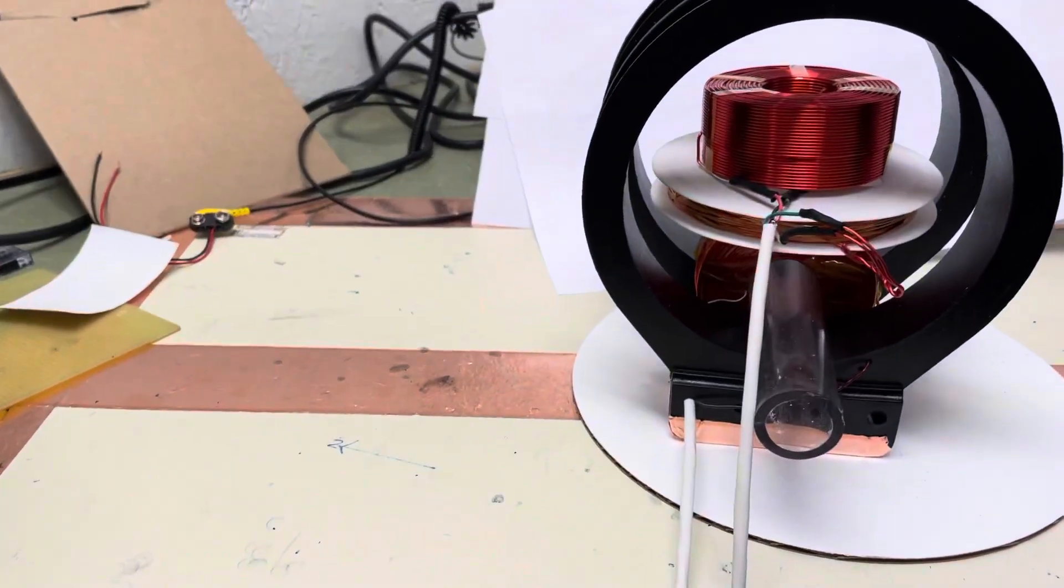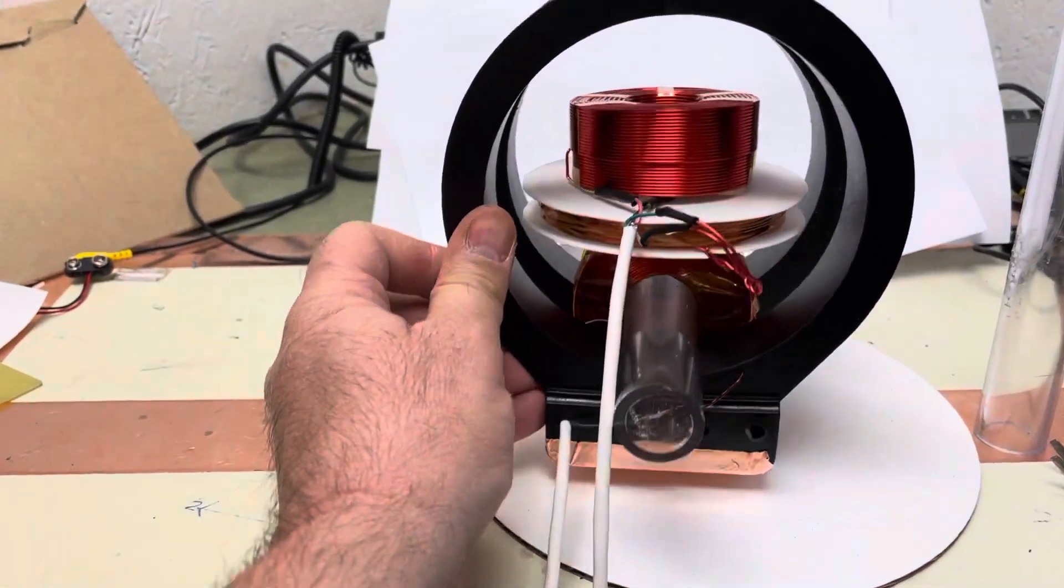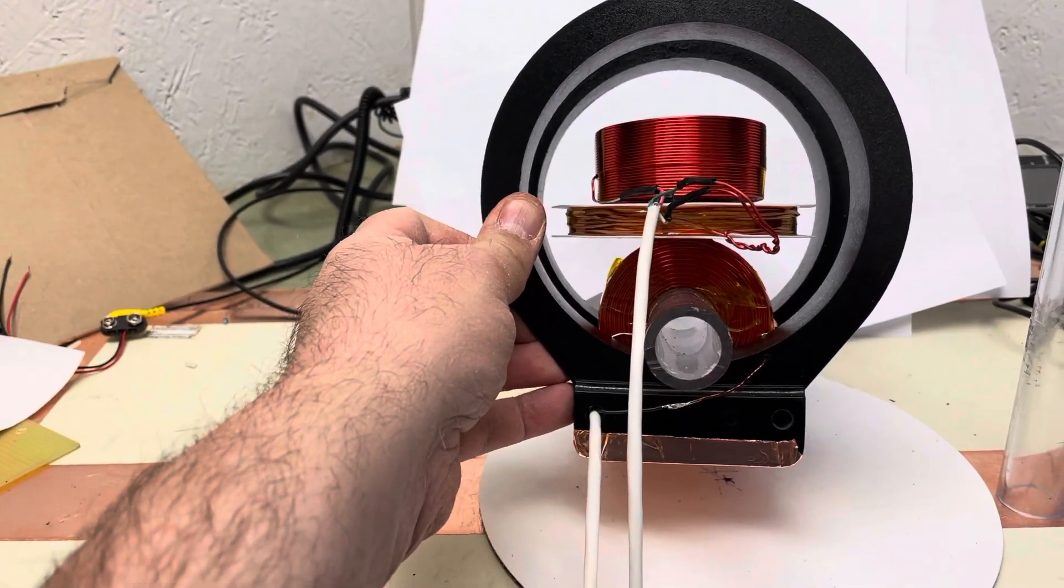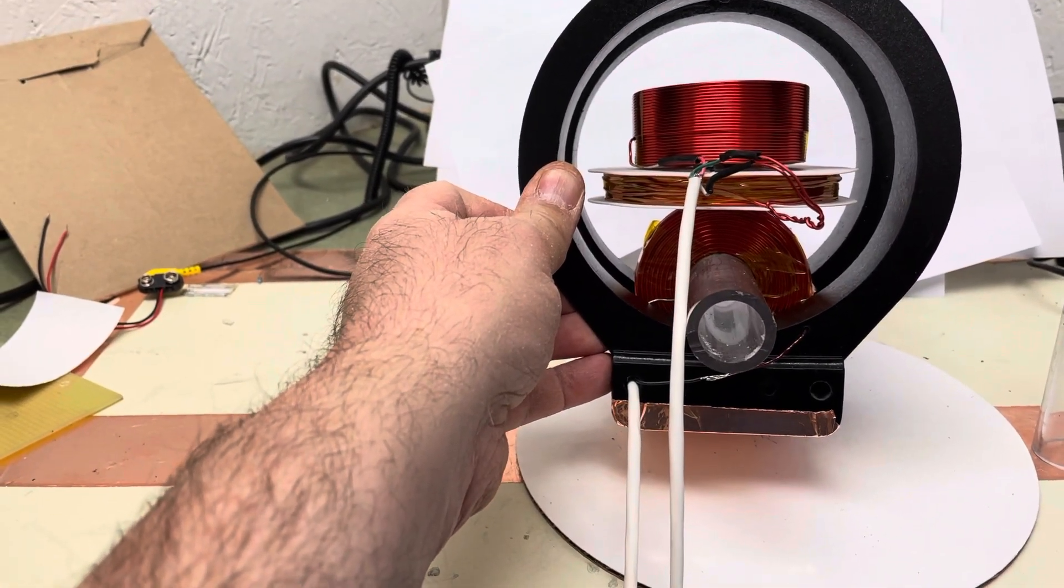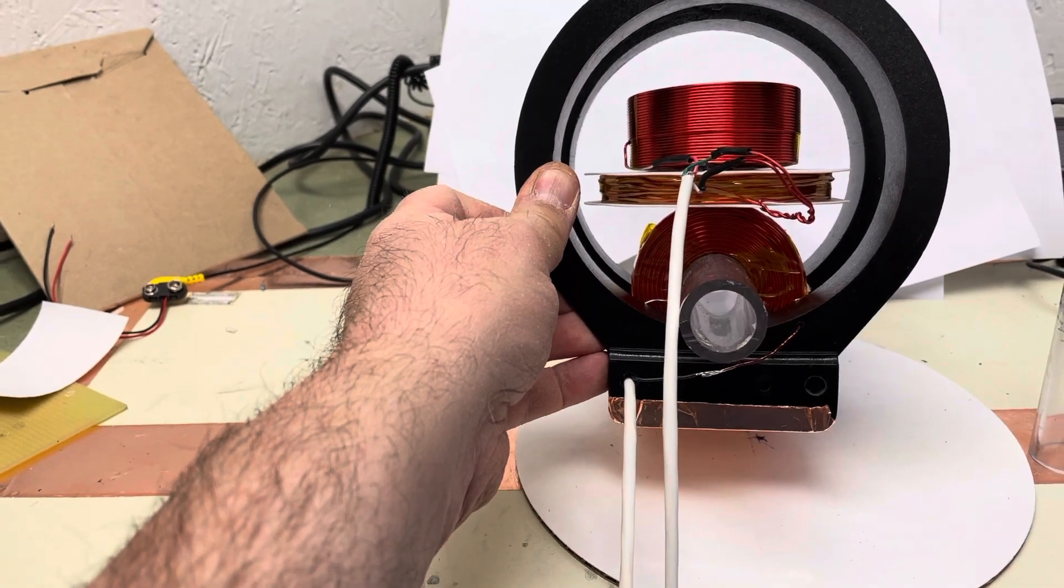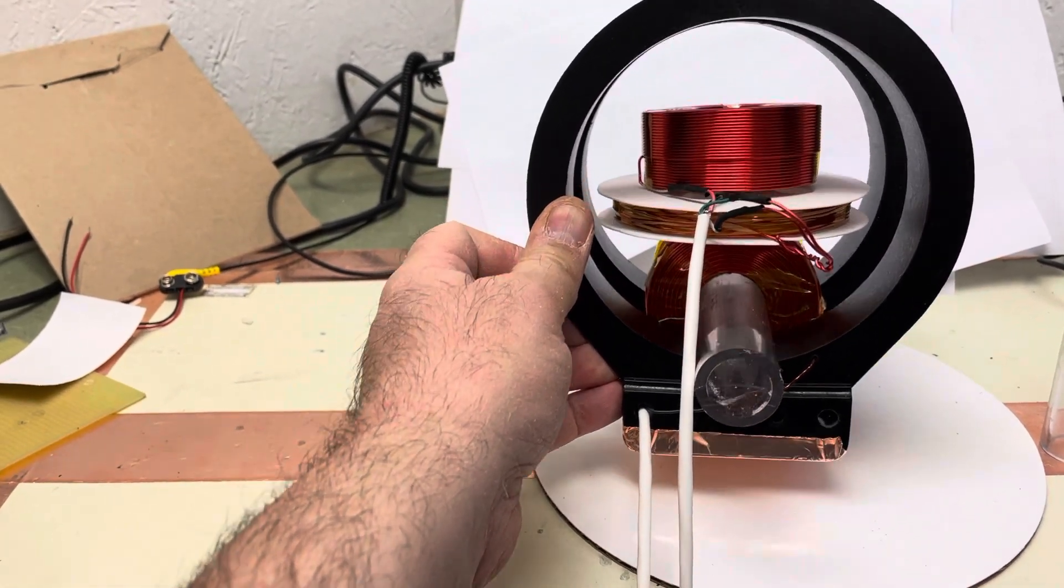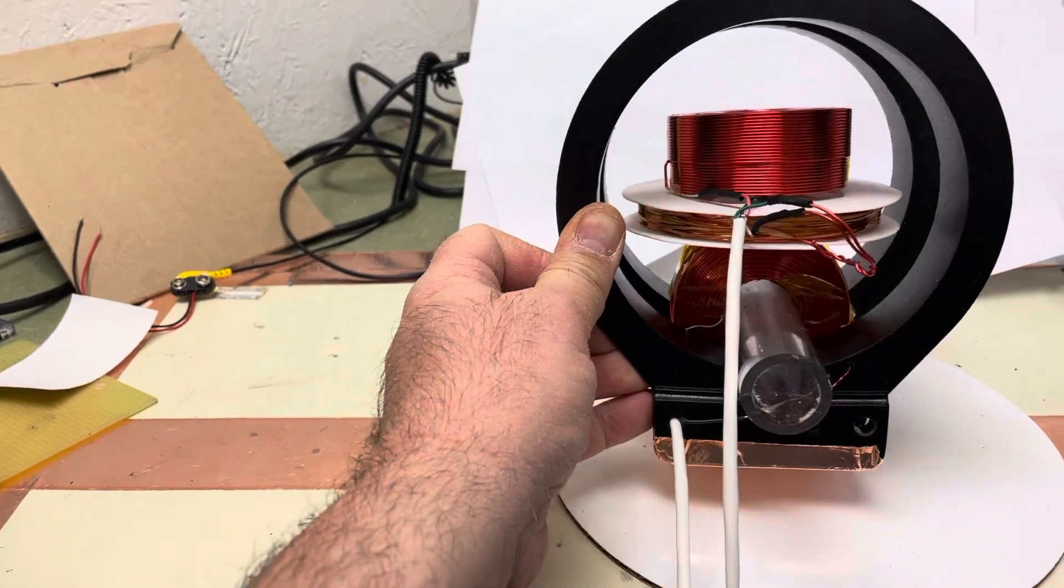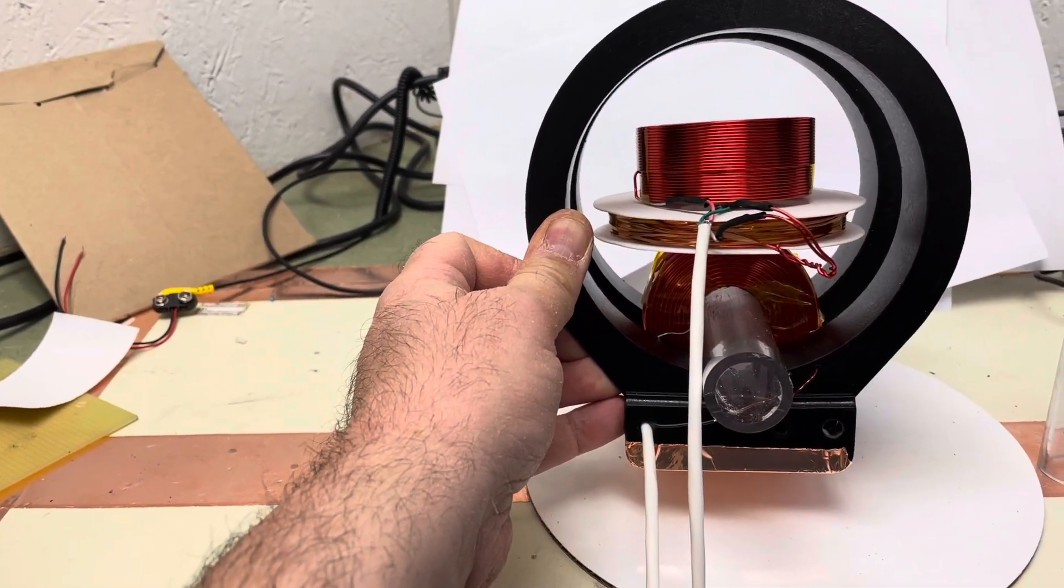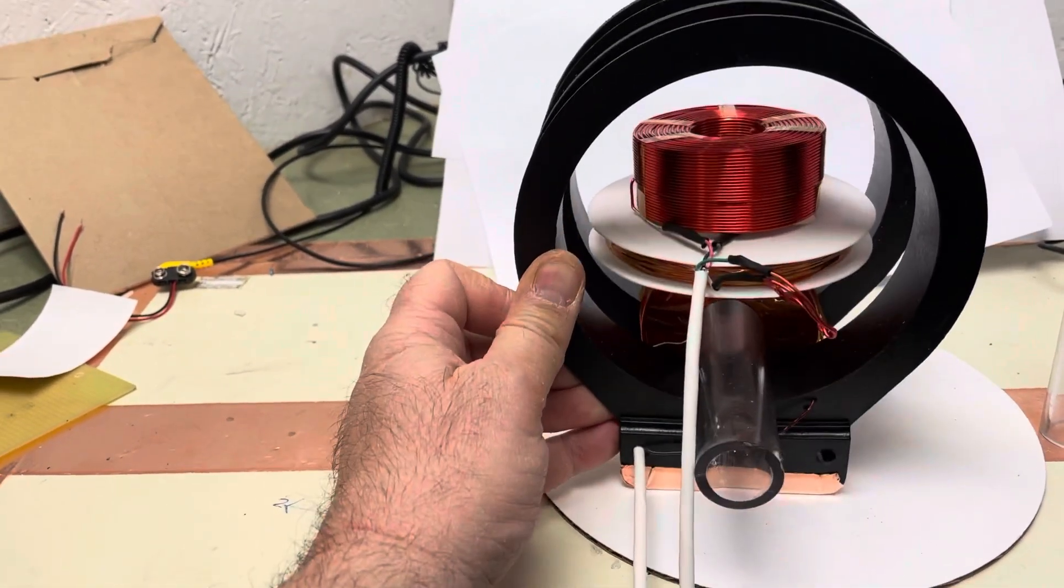So there's a gradient in the vertical direction. Then I have a shim coil which is meant to be used to either tweak the gradient or eliminate the natural field that the zero gauss chamber does not eliminate.